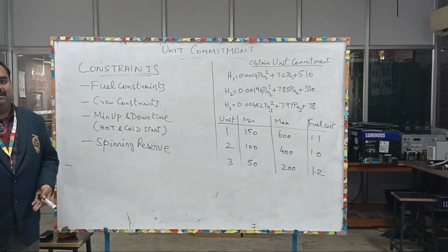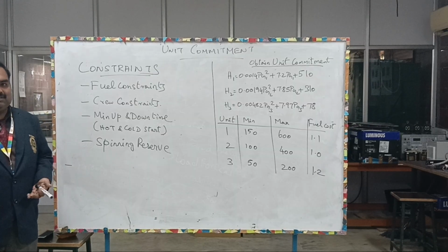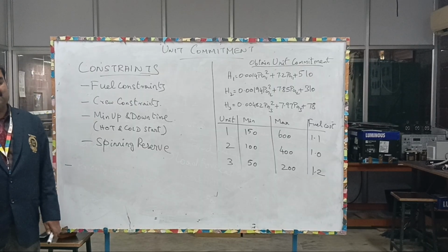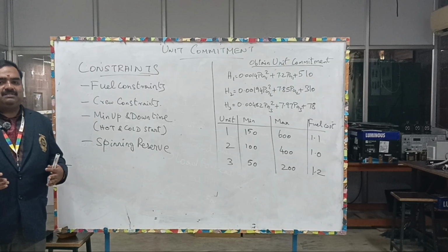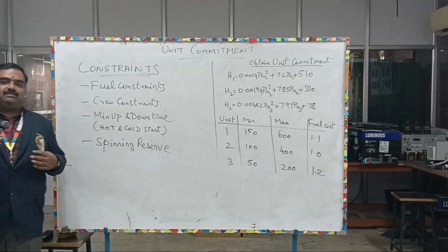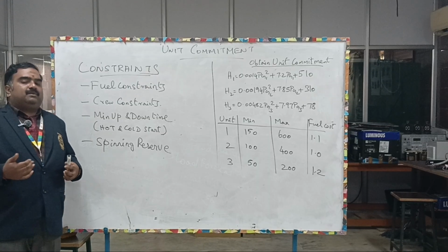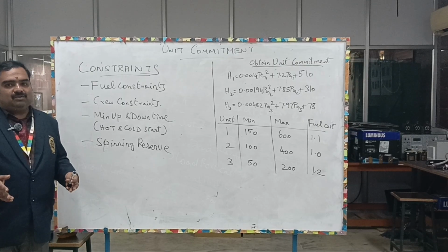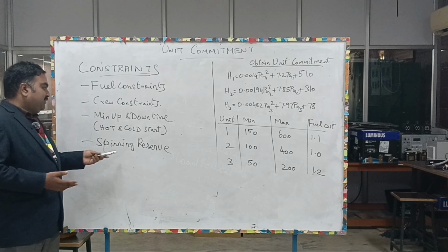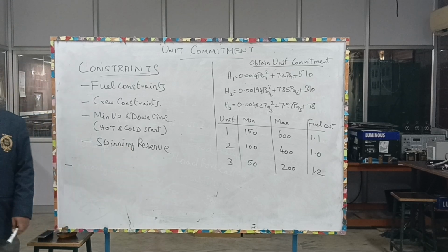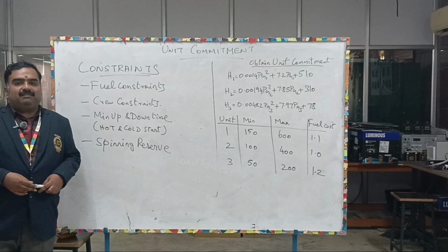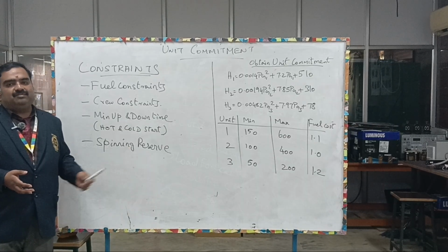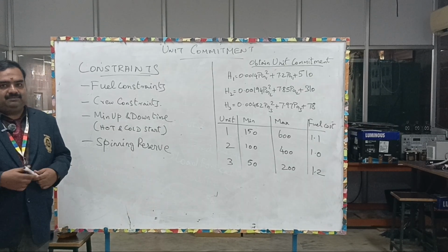That is very much possible in such a volatile environment like a power system. So, you always have to have a sufficient amount of spinning reserve, so that the dynamics of your power system are kept in place. Otherwise the frequency of the system will drop, and in order to restore that, you need to send power through the tie line to the neighboring areas, which is again a complex process. This can be avoided by having sufficient spinning reserve in the same power system, so that when there is a sudden rise in demand, this spinning reserve will take care of it momentarily, right.